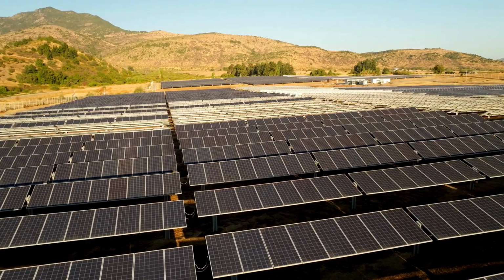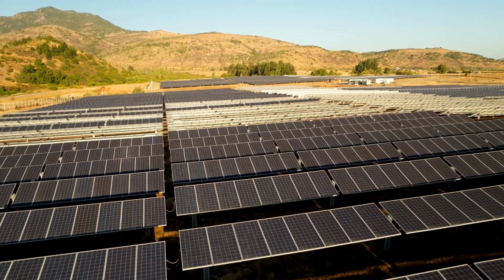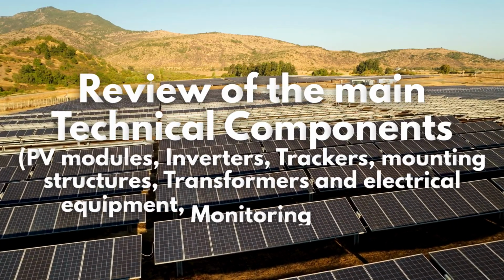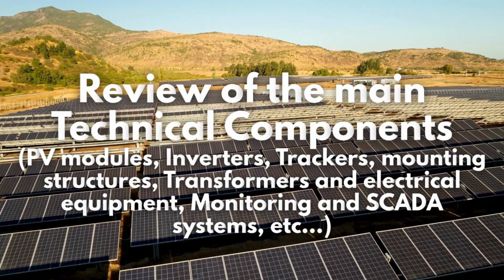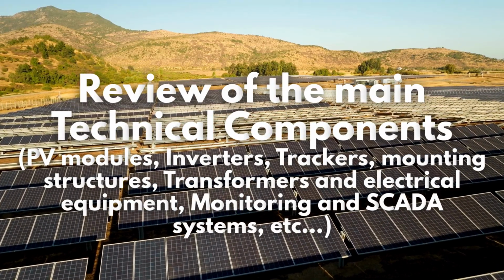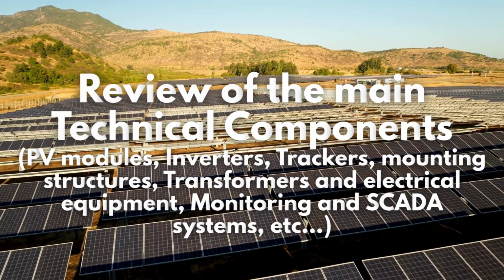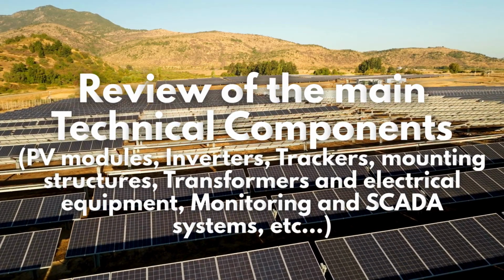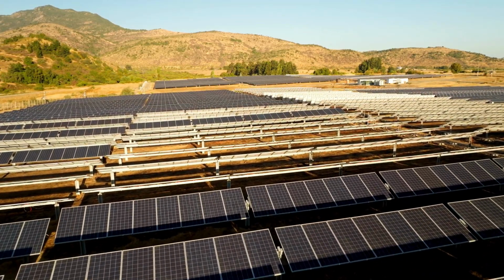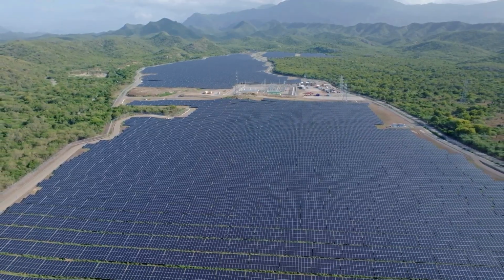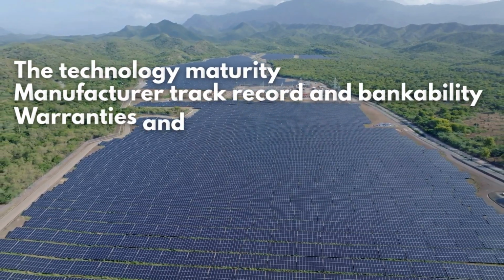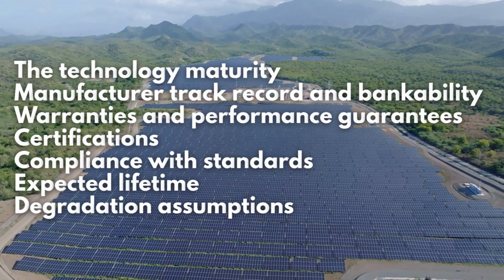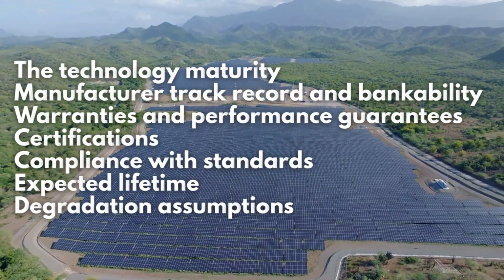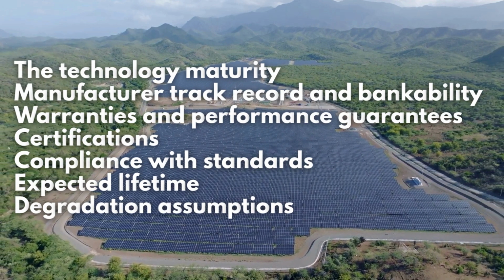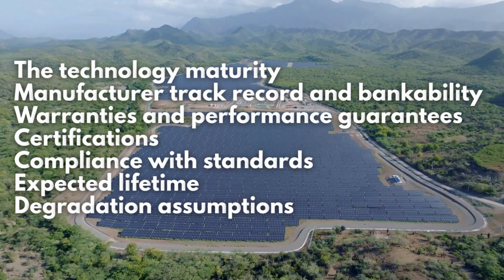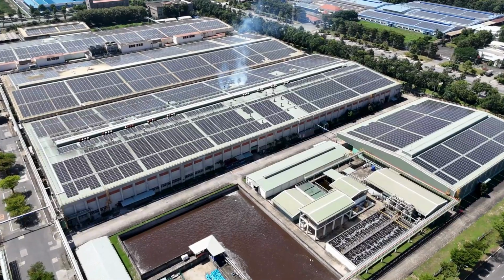Another core part of the technical due diligence is the review of the main technical components: PV modules, inverters, trackers or mounting structures, transformers and electrical equipment, monitoring and SCADA systems. The advisor will look at the technology maturity, manufacturer track record and bankability, warranties and performance guarantees, certifications and compliance with standards, expected lifetime and degradation assumptions. This is crucial because technology risk directly impacts long-term availability, operation and maintenance costs, and ultimately the project's ability to service its debt.